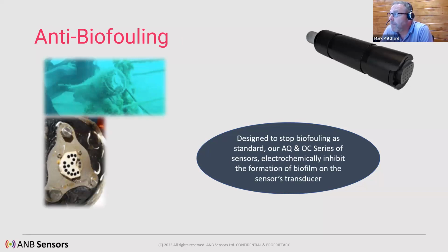As a byproduct of charging the chemical electrodes on the pH sensor, we produce a very, very small amount of hydrogen peroxide on the faceplate of the electrode, and that inhibits biofouling. The pictures you can see were taken from a deployment off the coast of Barcelona in the Mediterranean, which is very susceptible to biofouling. You can see biofoul on the casework of this, our old S-series sensor, but the actual transducer is clean. So you don't have to worry about biofoul with these sensors.